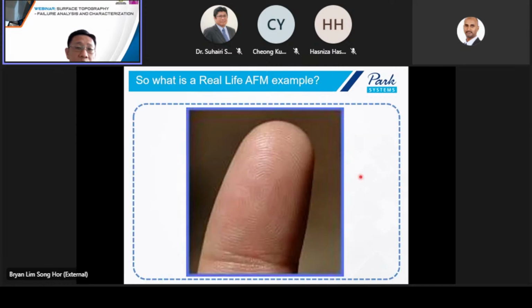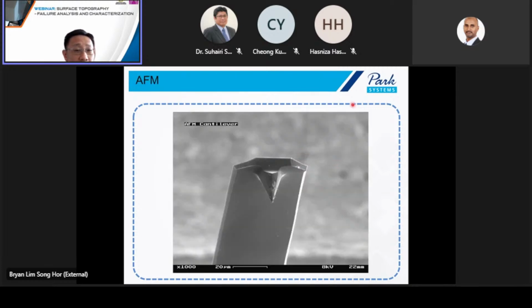Okay, so what is a real-life AFM example? The closest example I can think of is our finger. When we move our finger across a rough surface, we can feel that it's rough. When we move our finger across a smooth surface, like a mirror, we can feel it's smooth. Basically, our brain is like the AFM controller, which can distinguish whether the surface is rough or smooth. But in AFM, we don't use a finger, we use the AFM cantilever. The AFM cantilever is fabricated, most of the time from silicon nitride material, and it has a very sharp tip at the end.